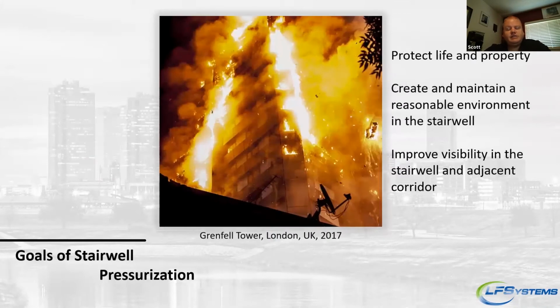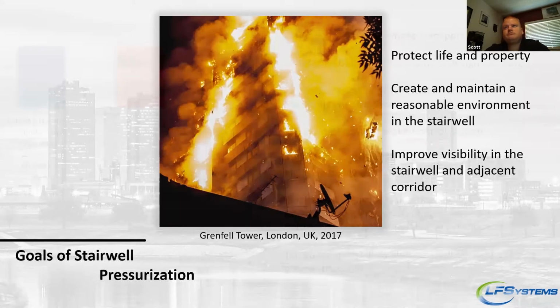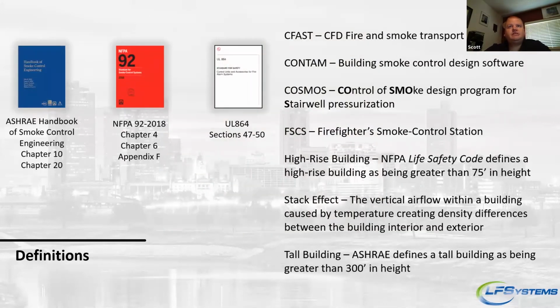So after this and several other tragedies, fire containment moved from historically being how to protect the building to how to protect life and the building. And the biggest way to do that is to create and maintain a reasonable environment in the stairwell. Here are some definitions that we're going to see in this presentation. They come from the ASHRAE Handbook, NFPA 92 and 101, and UL 864. The one you're going to see most in this one is the Firefighter Smoke Control Station, or FSCS.